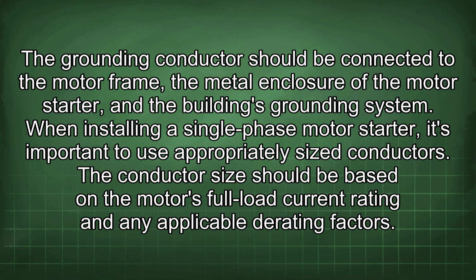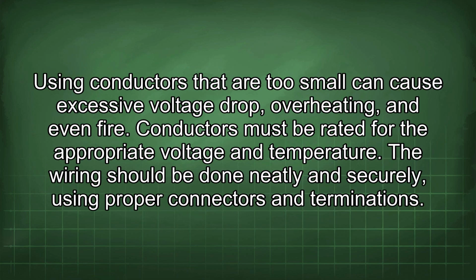grounding system. When installing a single-phase motor starter, it's important to use appropriately sized conductors. The conductor size should be based on the motor's full load current rating and any applicable derating factors. Using conductors that are too small can cause excessive voltage drop, overheating, and even fire. Conductors must be rated for the appropriate voltage and temperature. The wiring should be done neatly and securely, using proper connectors and terminations.